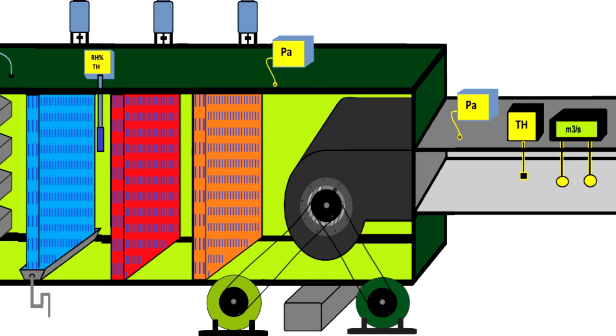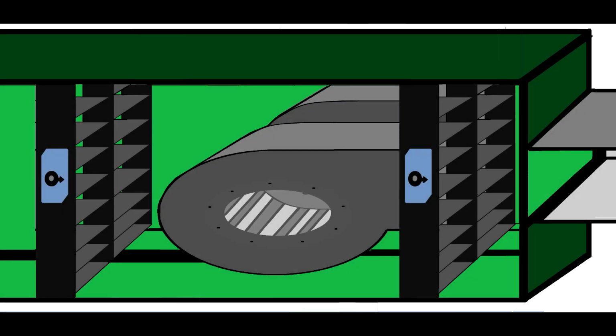Unlike the other one, this type of fan is better. It's belt driven. You always find pros and cons, but this fan will not generate as much heat because the motors are outside. This type of fan, scroll fans, generate heat inside. They have an internal fan as well.